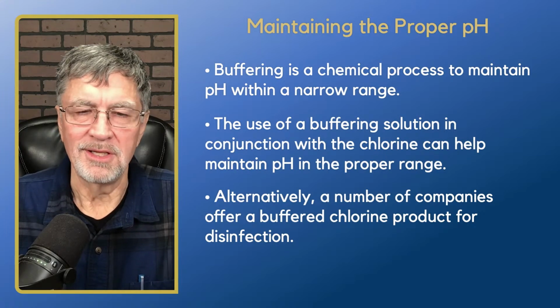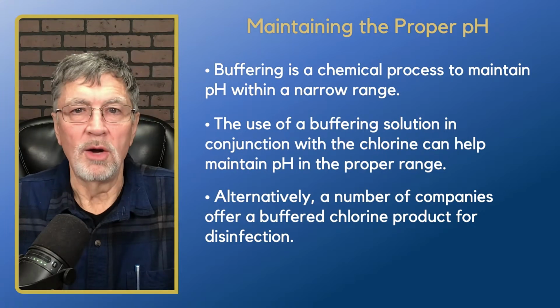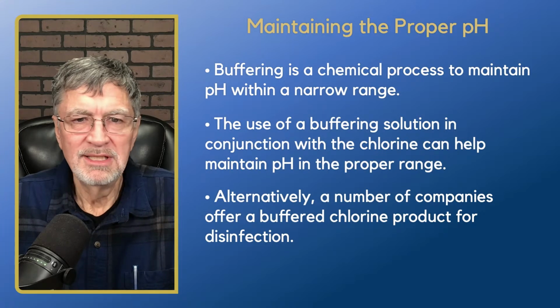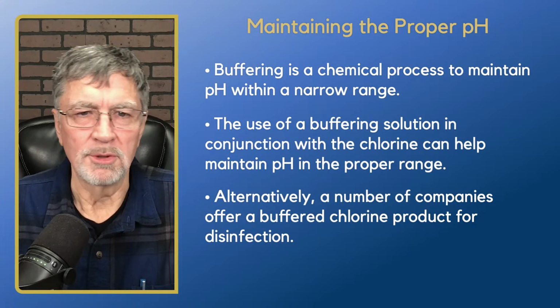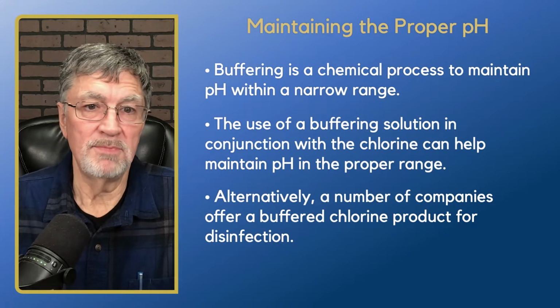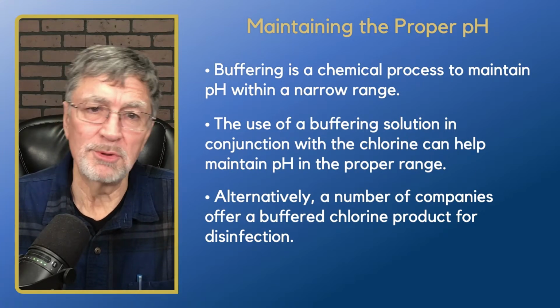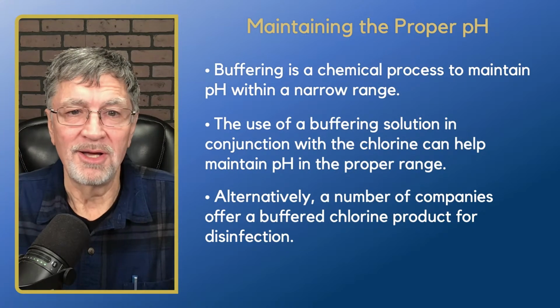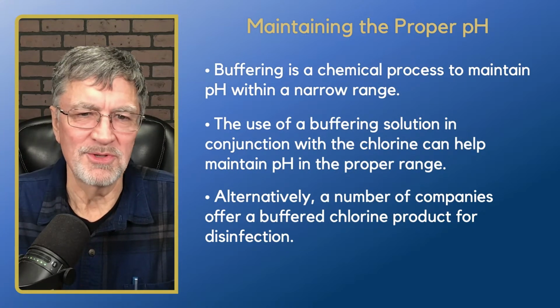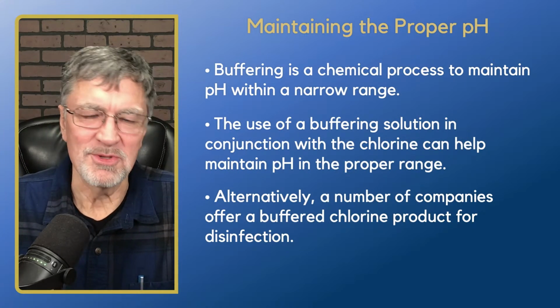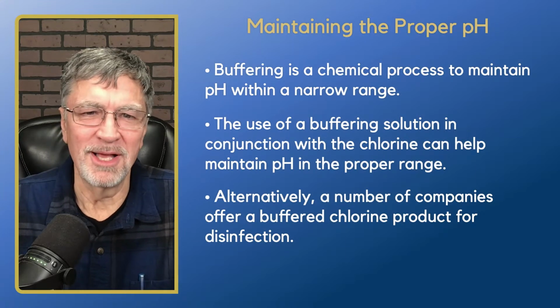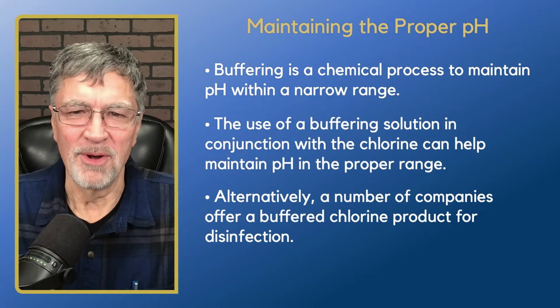And in the case of my story, we applied the buffering solution, and the total coliform cleared right up. So it was a pH control issue right then and there. The solution was pretty simple, and I learned an incredibly valuable lesson that has stayed with me. So I can't emphasize that enough here. Don't be like me and learn it the hard way. Do it the right way from the start.